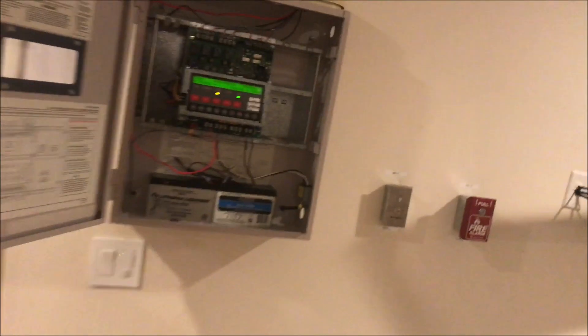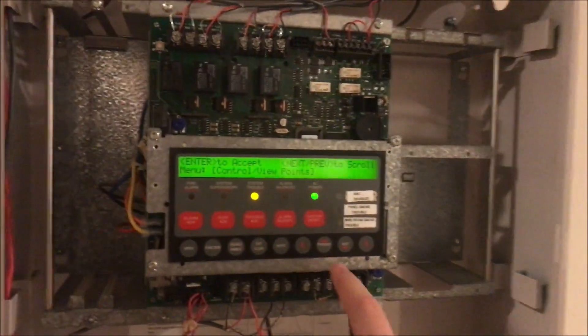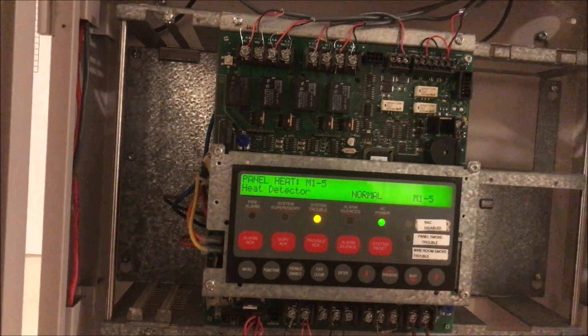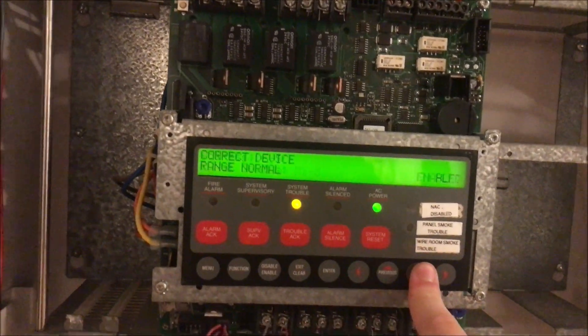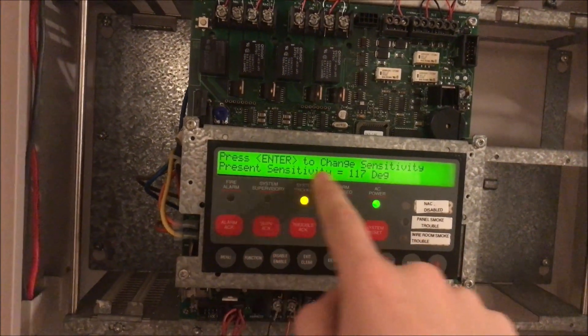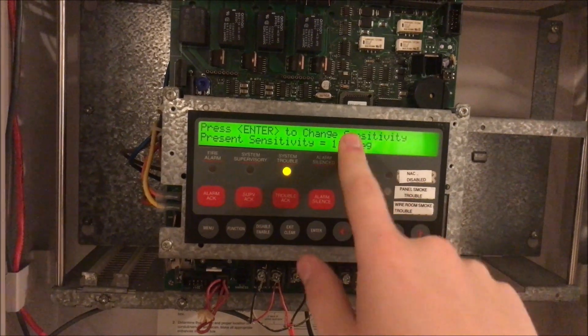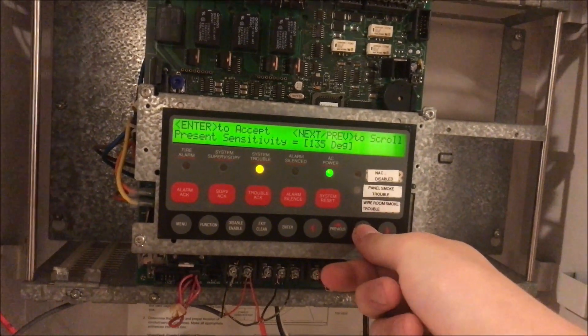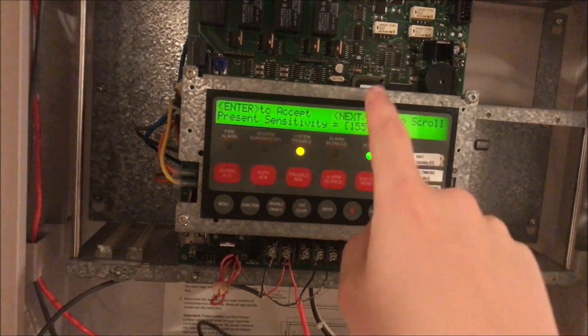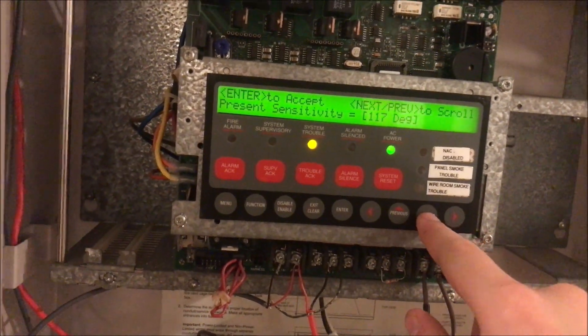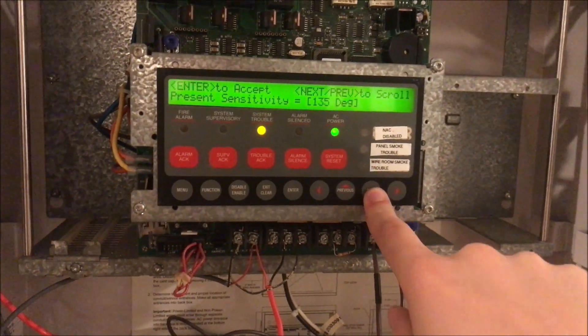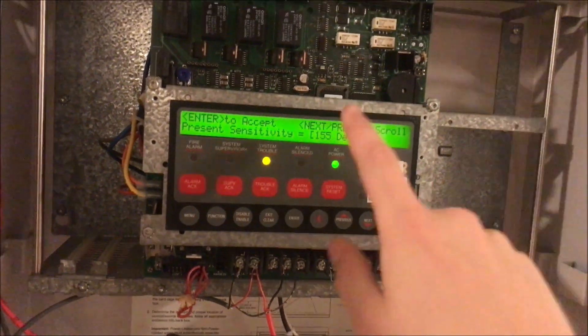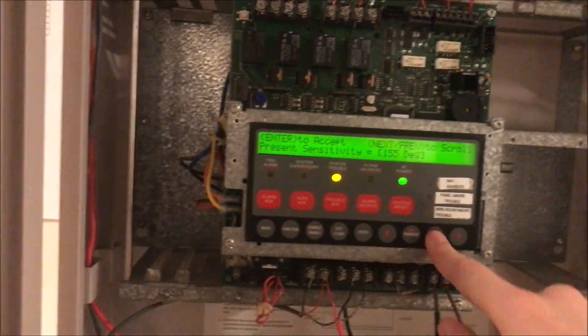The way that Simplex does it is you can actually go into the heat detector and see information about it. You can see that the sensitivity right now is 117 degrees - that's when it will trip. But you can actually change it for different applications. You can have it set at 117 degrees, 135 degrees, or 155 degrees, and you tell the panel and it will tell the heat detector how to read temperature.